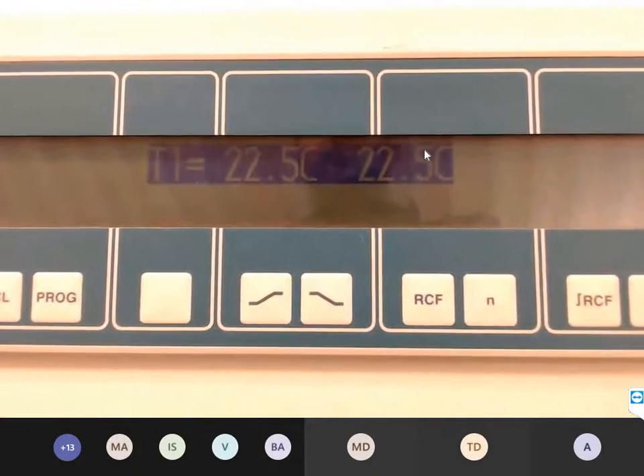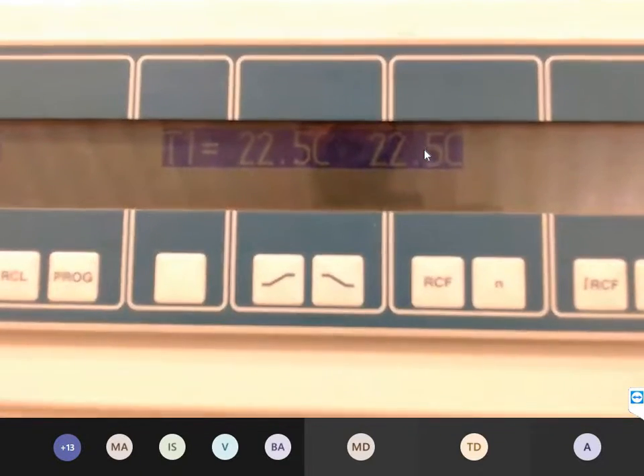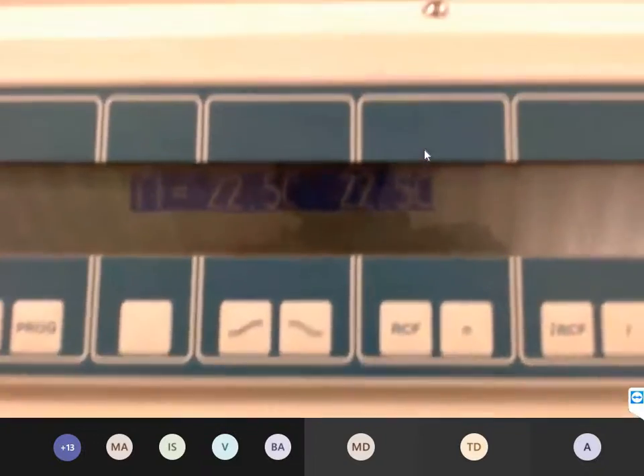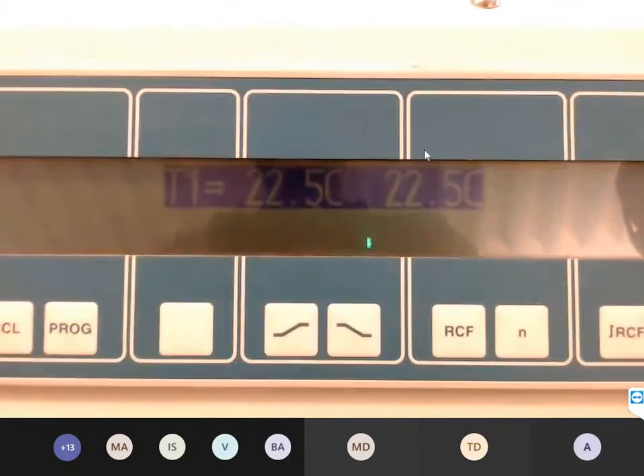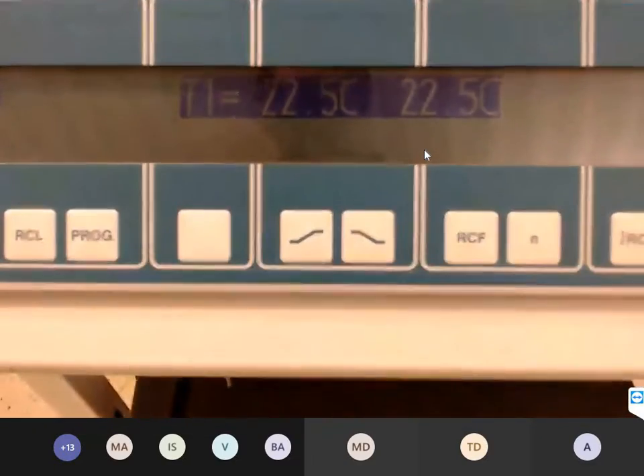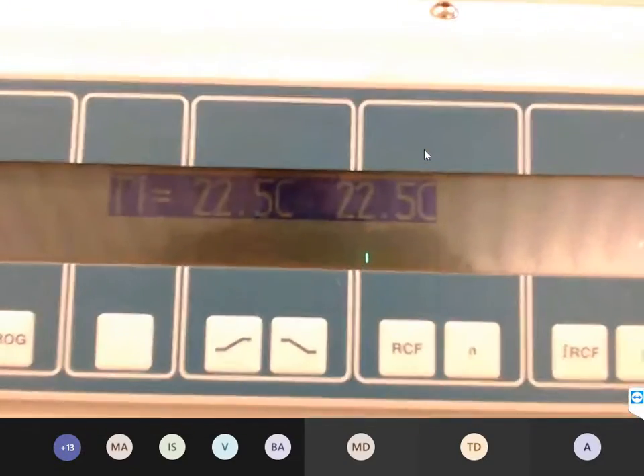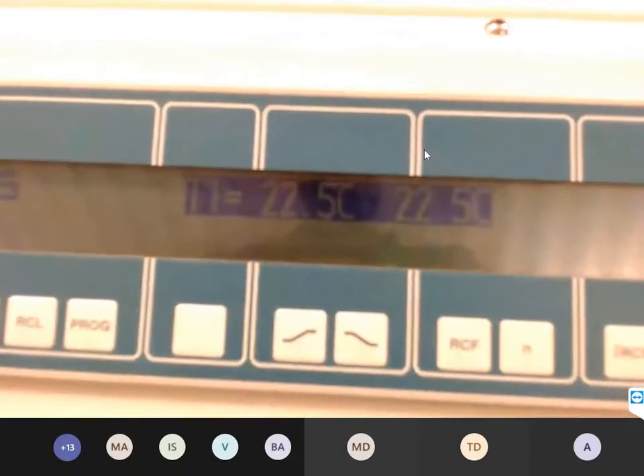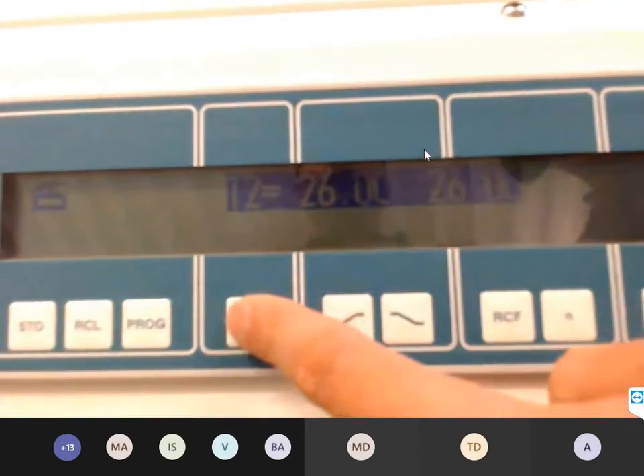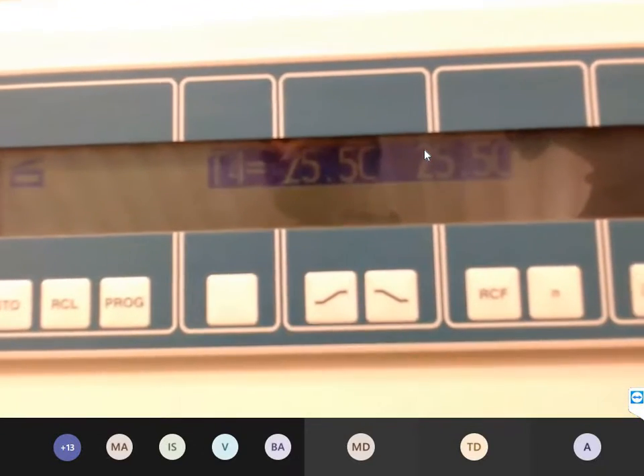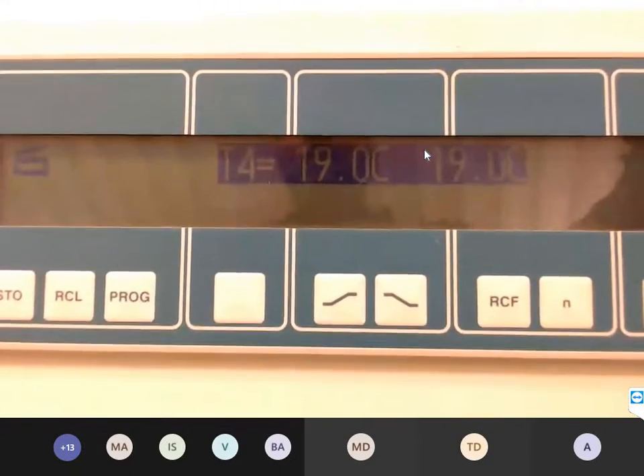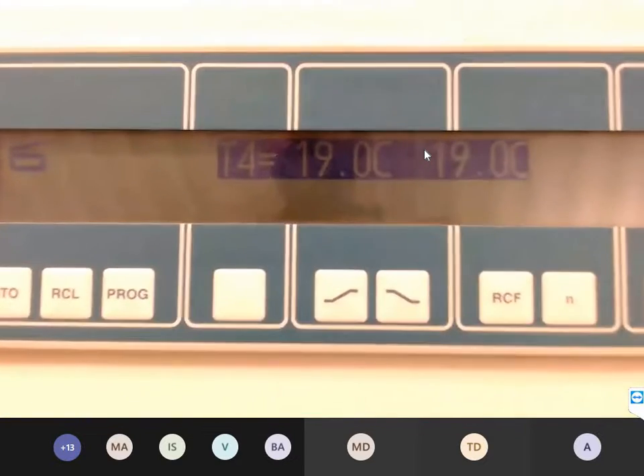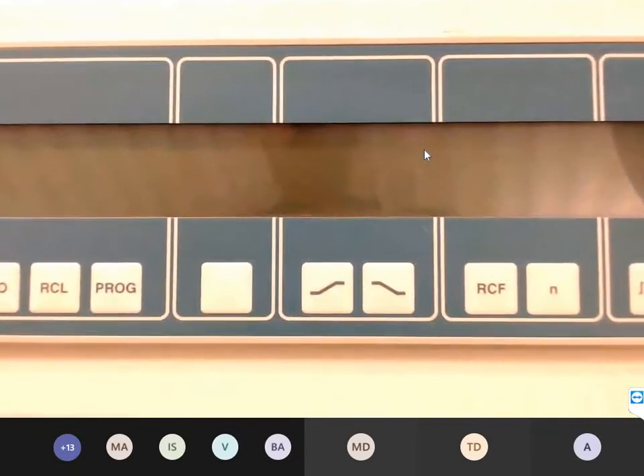So same procedure like the small centrifuges. If you need the values, please write us an email with the serial number and the type number of the device, and then we can send you the manufacturing protocol. On the manufacturing protocol, you can find the settings, the offset values, T1, T2, 3, and 4. Quite easy. Switch off the device and change the jumper position for the normal mode.